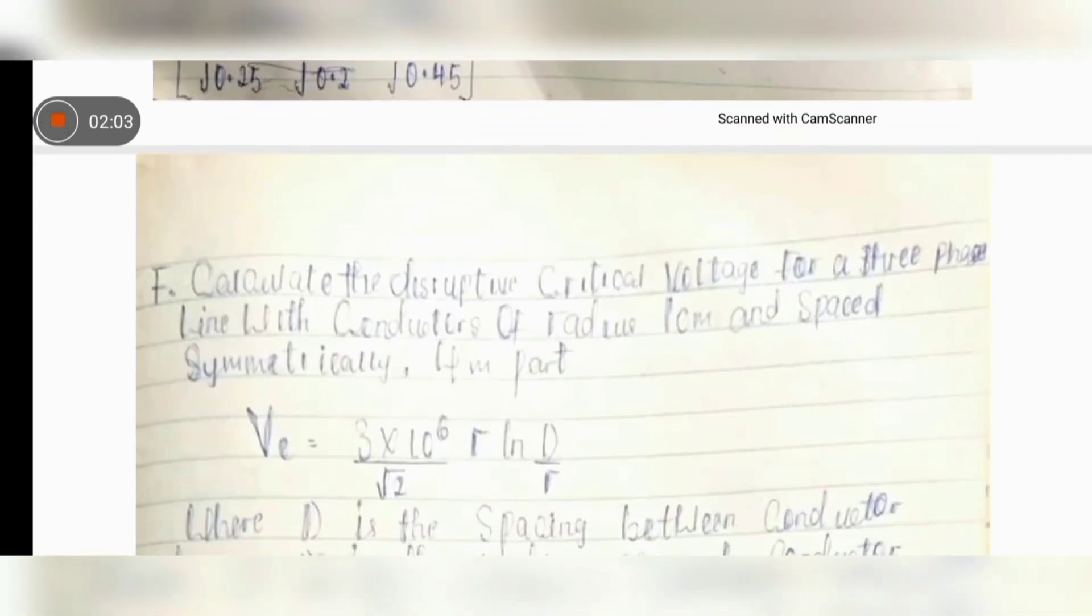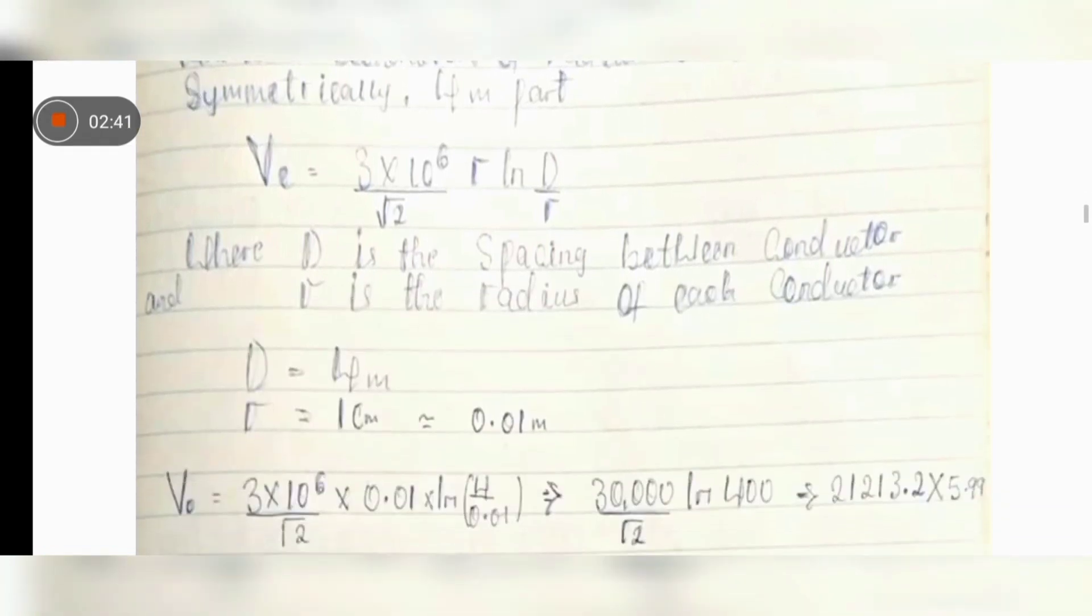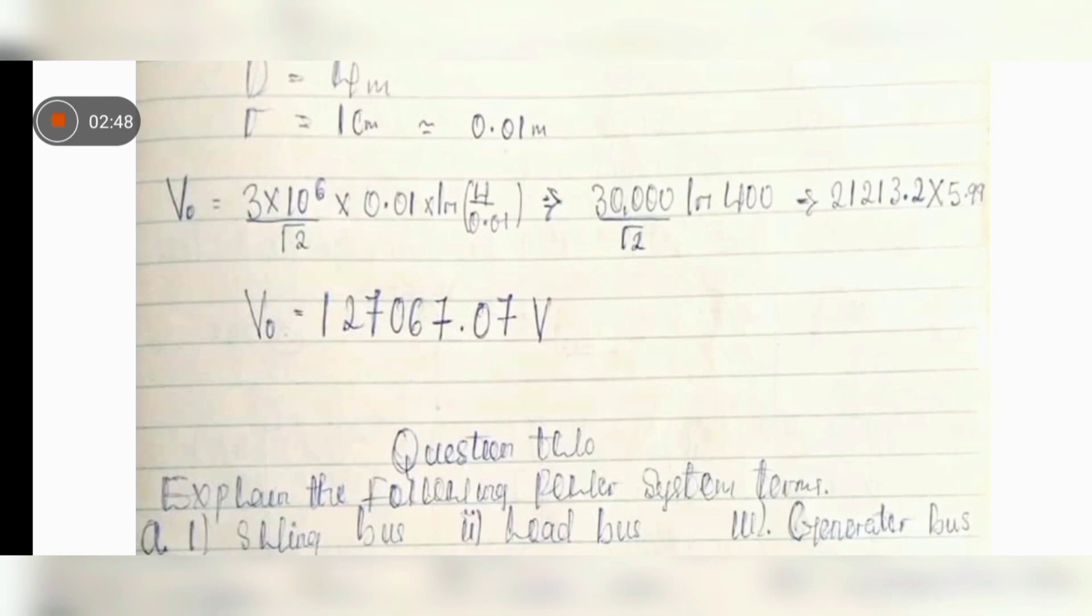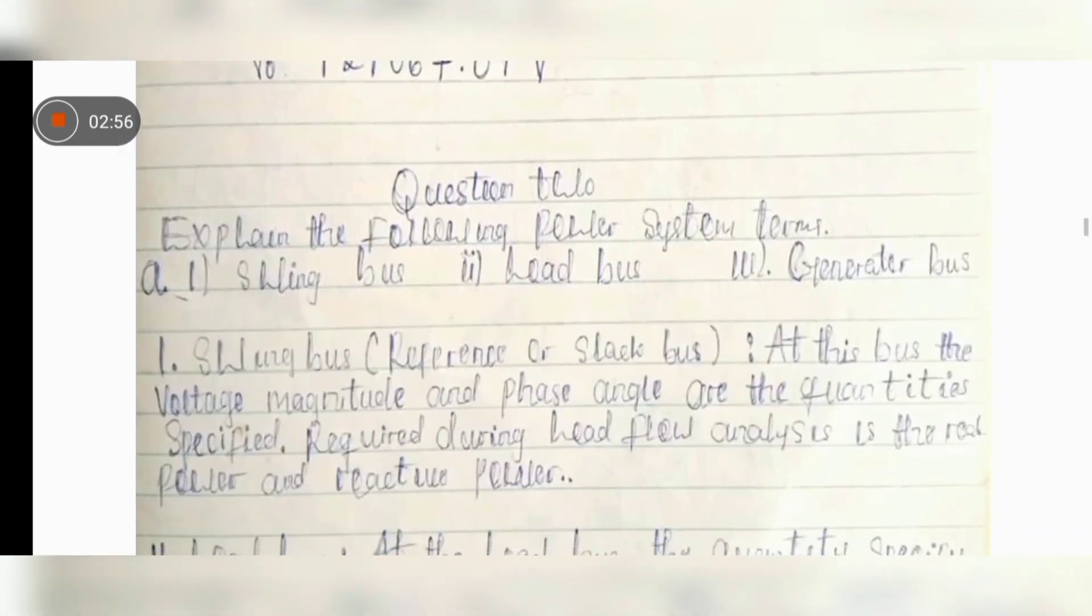Calculate the disruptive critical voltage for a three-phase line with conductors of radius one centimeter and spaced symmetrically four meters apart. Mind you, the four meters apart there is the distance space. The radius given to us is one centimeter. We have to convert it to meters by dividing that one by hundred. We have our meter for that. And the formula for finding critical voltage is equals to 3 times 10 raised power 6 over root 2, radius, ln of d over r, that is our spacing over the radius. So if you can input the values, you should have your final answer as 127,067.07 voltage as your final answer. If you have that, put that in the comments below.